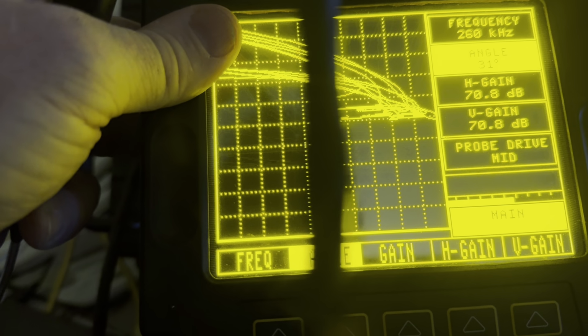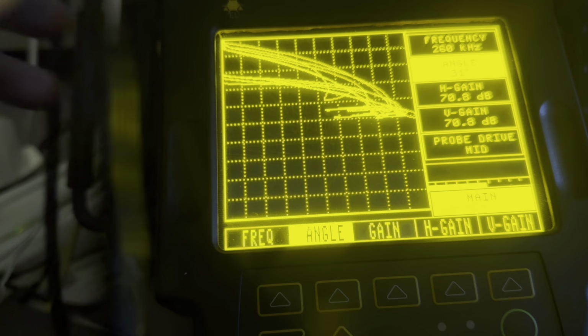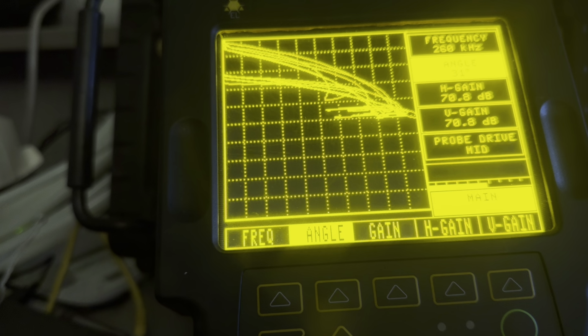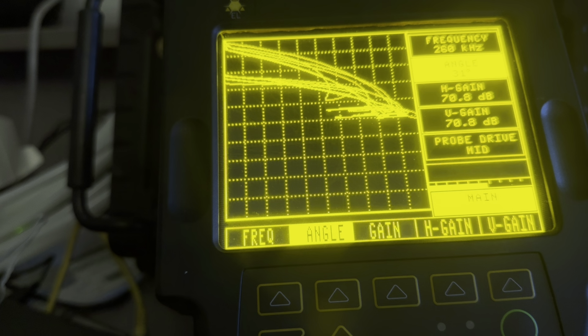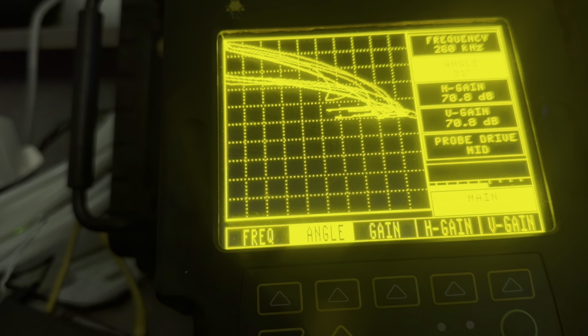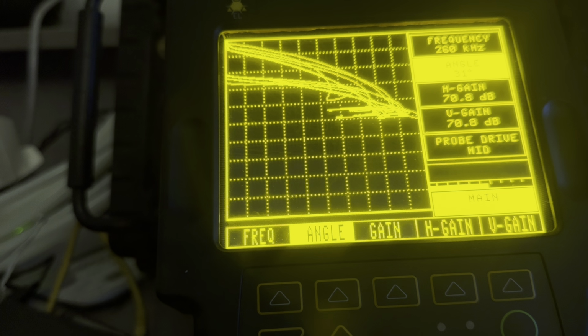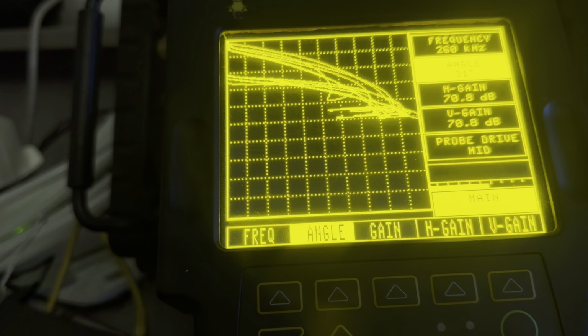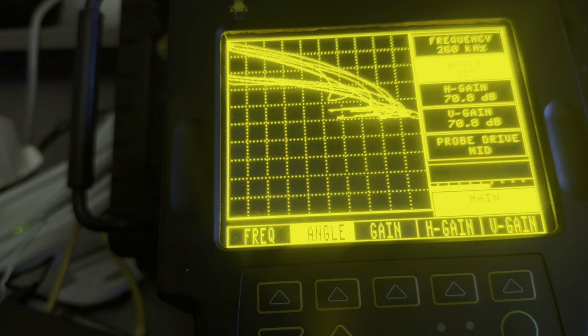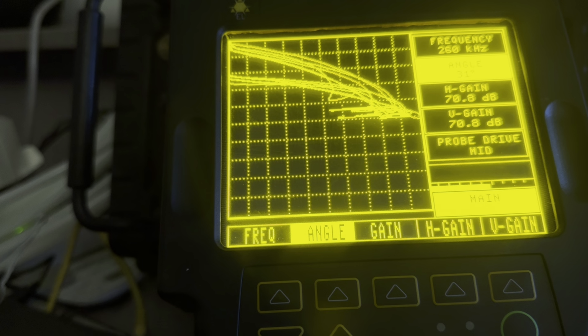Now, if I was using the Nortec 600D advanced model, and I wanted to hook up a probe with a BNC connection, and that's a coax cable, there's actually a setting in the operator selectables where you change the connector type from Lemo to BNC. And I've seen with that instrument, whether or not you change that setting, you may get some active signals, but there are other times when you actually have to have it selected for the probe to work.